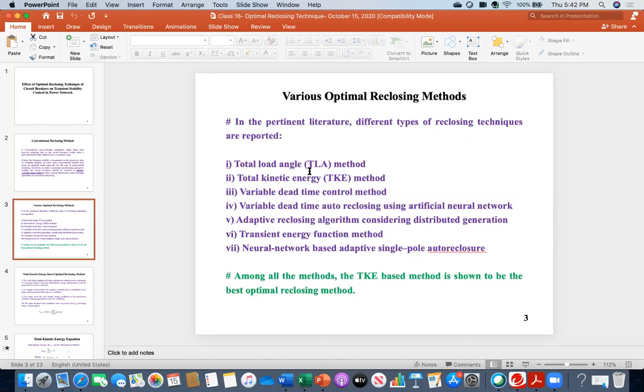There is the total load angle method, called TLA, the total kinetic energy method, the variable dead time control method, variable dead time auto reclosing using artificial neural networks, adaptive reclosing algorithms considering distributed generation - for example, if you have distributed generation like solar or wind energy, you need a different technique - the transient energy function method, and the neural network based adaptive single pole auto reclosure method. These are the optimal reclosing methods.